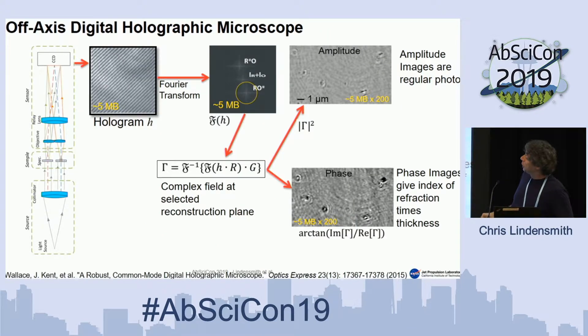So how the holographic microscope works — it looks a lot like a regular microscope. We've got a light source, an objective lens, our sample, and a detector. We use very simple objectives because we're using monochromatic light, so we don't need chromatic aberration correction. We have a second beam that we use as a reference — basically we put water in there and get an interference pattern. Our second beam hasn't gone through anything but water, same path length, so we know exactly how long it should have taken. The sample — whether it's got bugs or rocks or something — has perturbed that beam, and we can back-propagate to figure out what was in the sample. We take some Fourier transforms, multiply by a phase factor, and reconstruct an amplitude image that's just like a regular picture. Or we can reconstruct a phase image, which is essentially the thickness of the sample times the index of refraction difference between the sample and the medium. Basically the entire electric field is captured; we can combine these into any form of image without putting any stains in. The catch is we don't get the chemistry out.